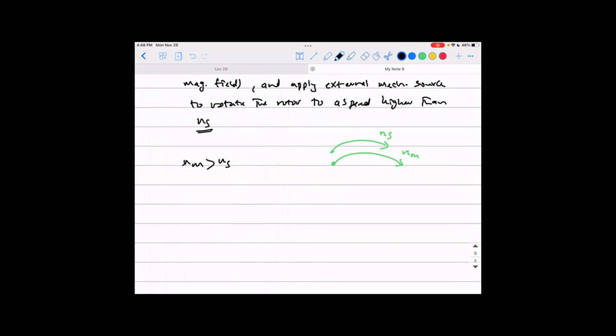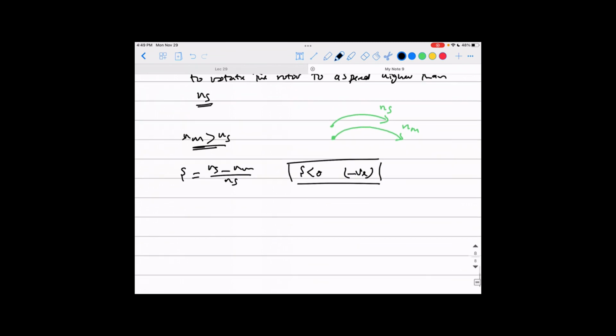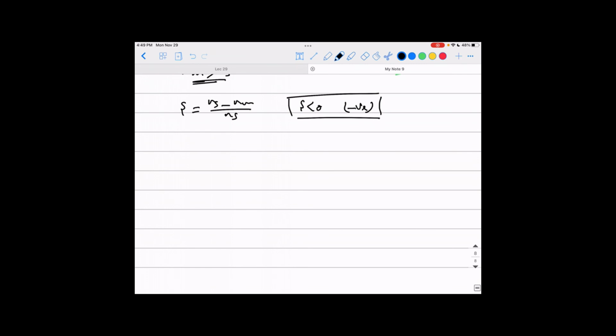So the 3-phase voltage applied to the stator will create a magnetic field that is rotating around the circumference of the machine at the synchronous speed. So for the machine to act as a generator, you have to apply a mechanical source and make the speed high enough to be higher than the synchronous speed, and like that, it will turn into a generator. If you want to calculate the slip here, which equals ns minus nm over ns, you will find the slip to be less than 0, negative slip, because the mechanical speed is higher than the synchronous speed. And that's how you know it's generator mode: the slip is negative. It's very weird to us because we didn't use to this, but yeah, you can find it if you're dealing with a generator mode. Okay, guys?